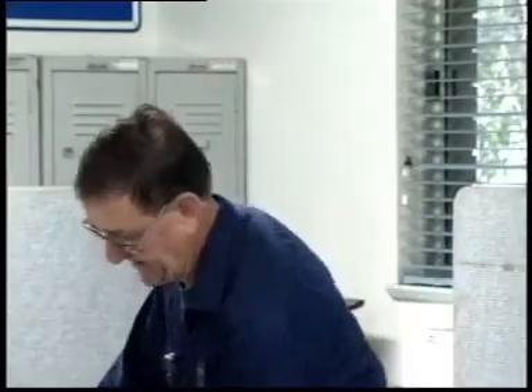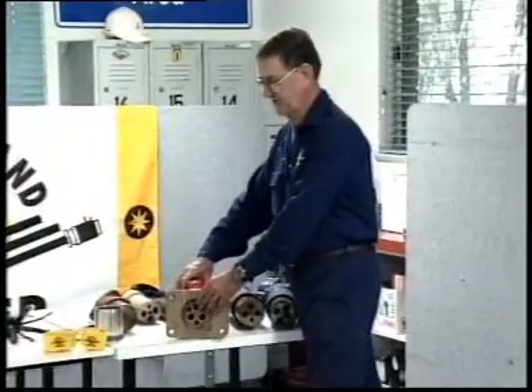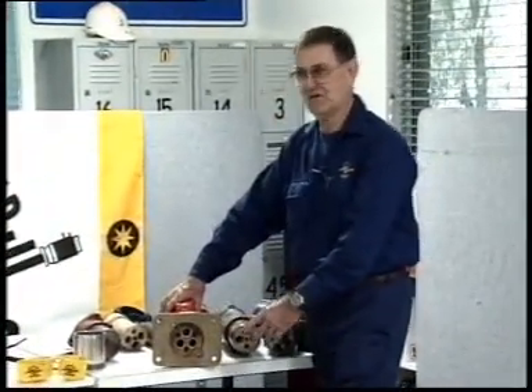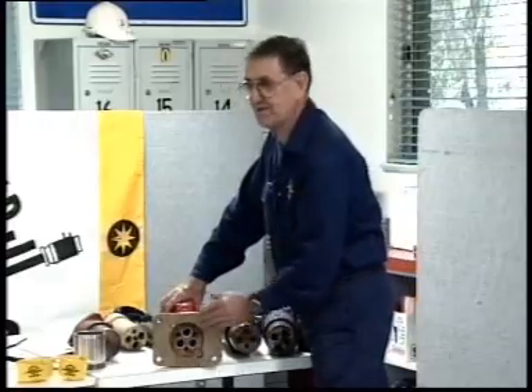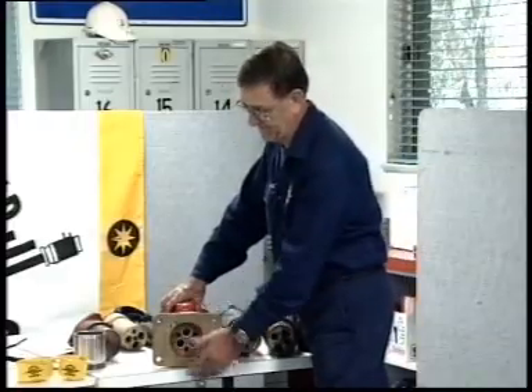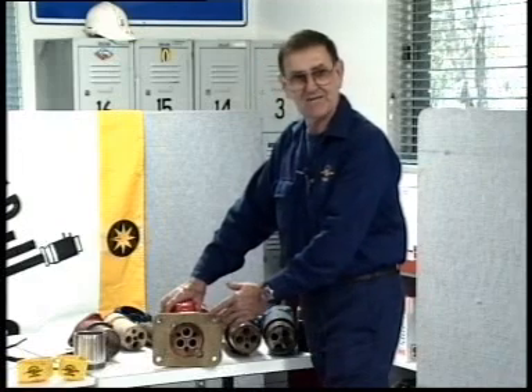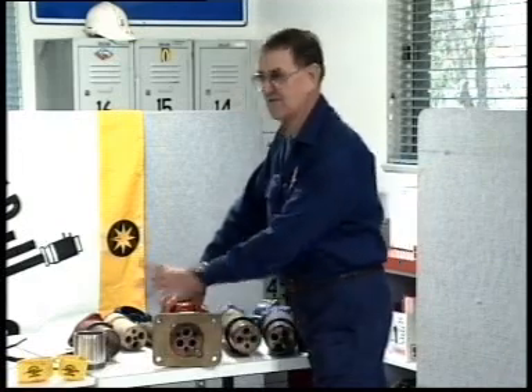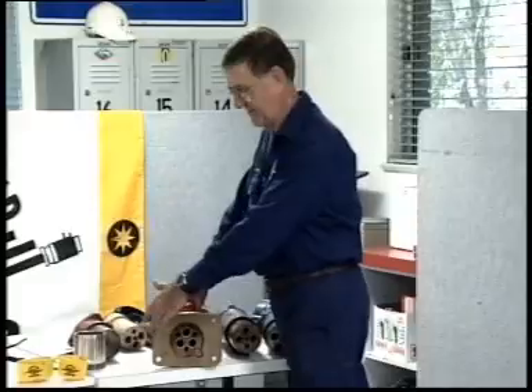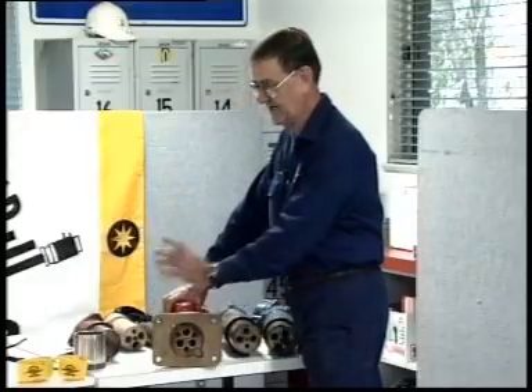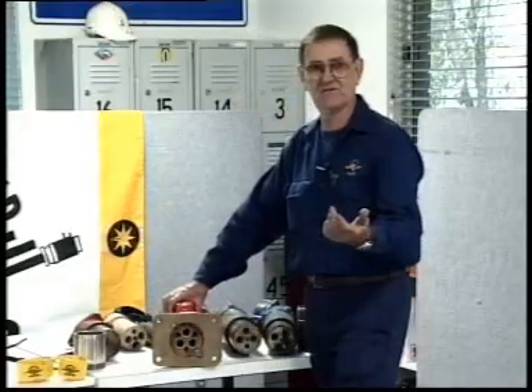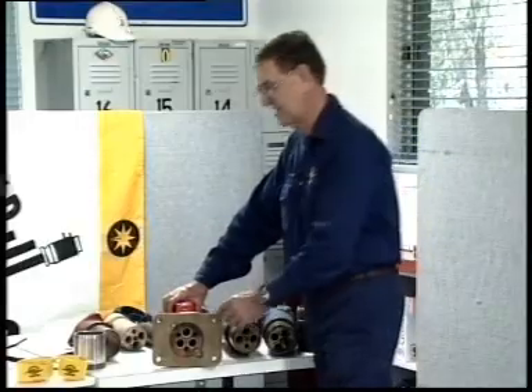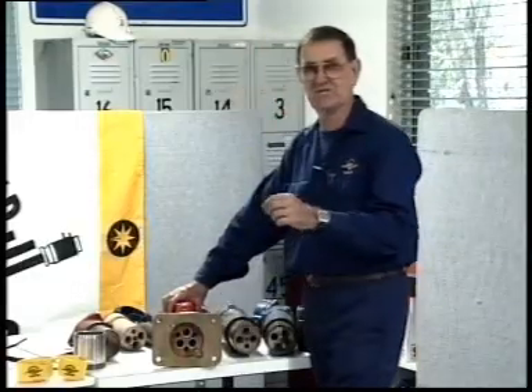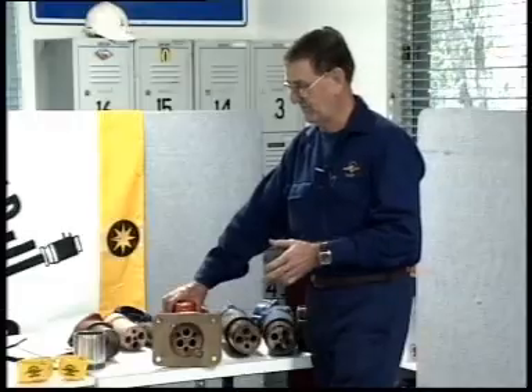So that's a flame path, that area there, and where that bolts onto is a flame path. So if it happens to be slightly loose, the electrician has to ensure that there's no grit or dirt down the back there, because you'll damage this flame path, and if you damage it in any way, then some of the flame could get out through that section and be hot enough to get outside to create a problem. So he's the one that has to do it, and he gaps it. You see him going around on various shifts with his feeler gauge, checking those flame path areas to make sure they're not outside what the standard calls for.